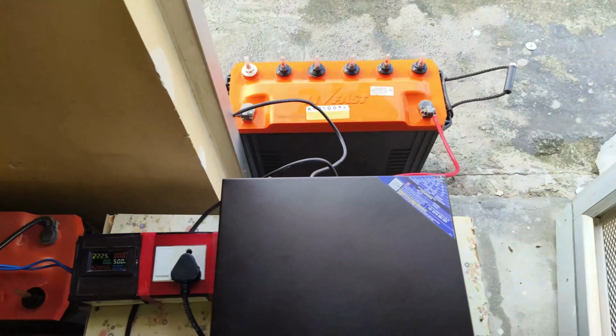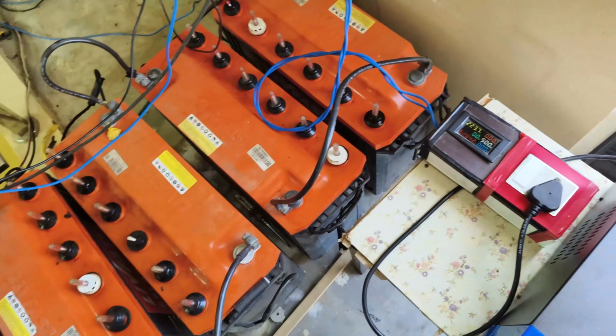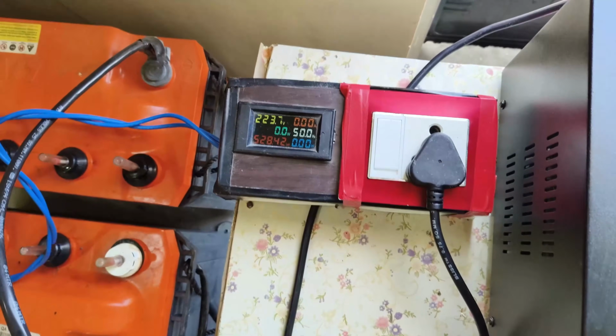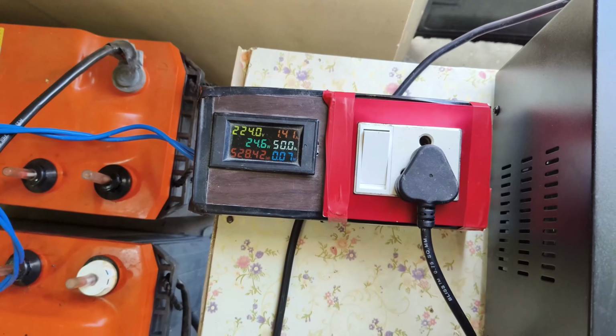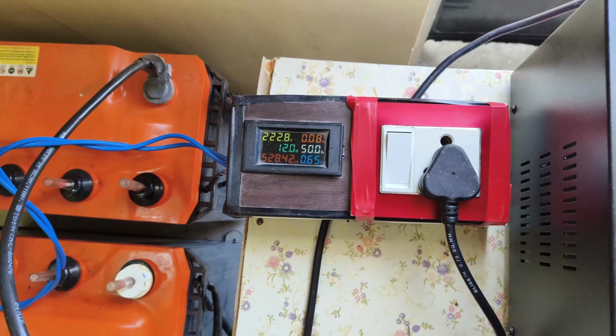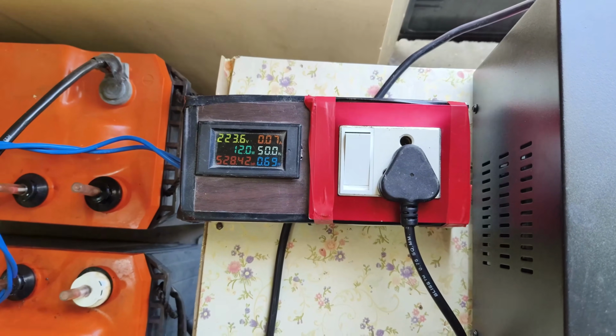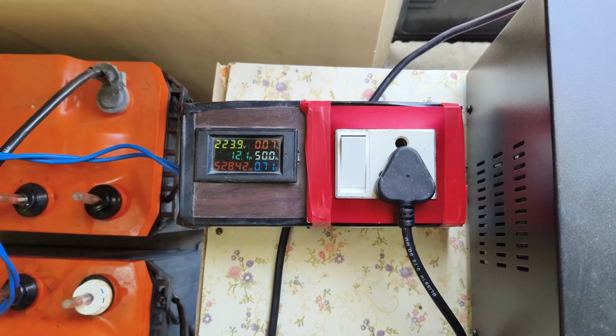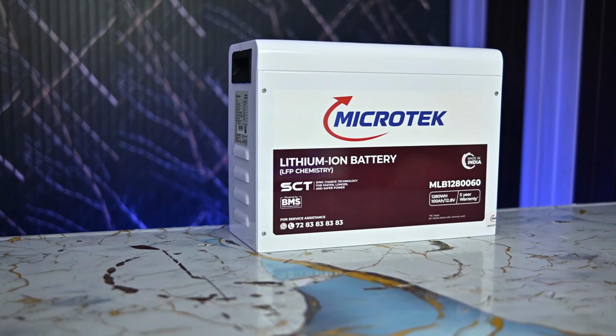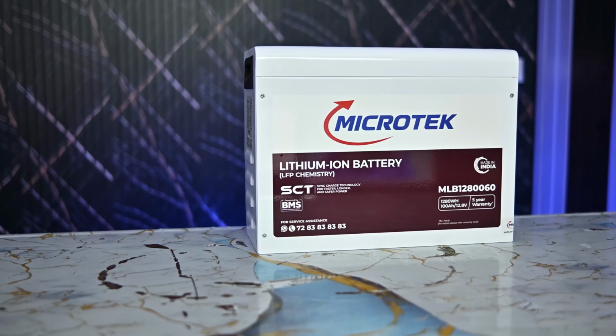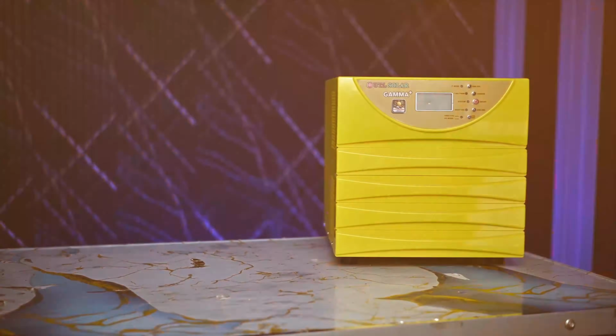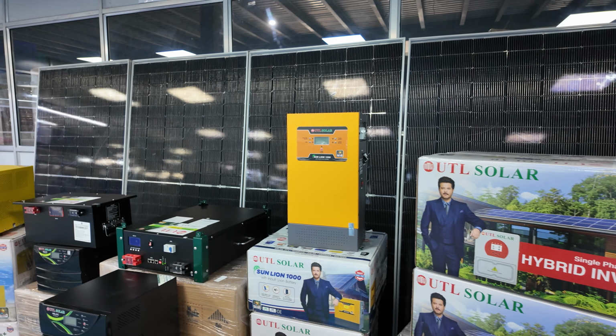But if you run a 500 watt load only on the battery, it will run for around 1 hour to 1.5 hours. This happens because you cannot run a very heavy load on a lead acid battery. If you run a load of around 300 watts on it, then you can get a backup of about 3 hours, but 500 watts becomes too heavy for a single lead acid battery. Instead of that, you can use a 12.8 volt and 100 ampere hours lithium battery. With this battery, you can get more than 2 hours of backup on a 500 watt load, and for this reason, I recommend choosing an inverter that supports lithium batteries or one that comes with a built-in lithium battery.